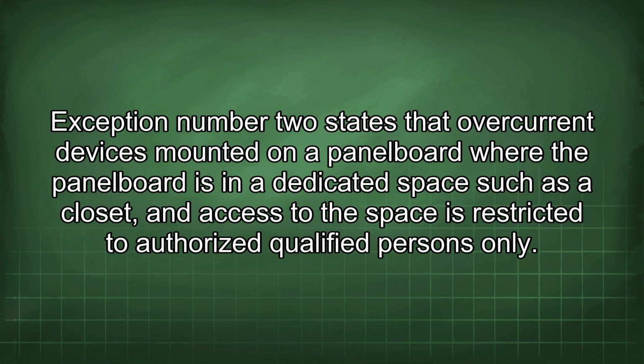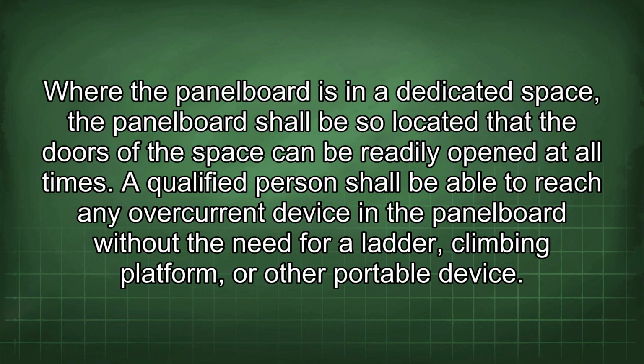Exception number 2 states that overcurrent devices mounted on a panel board, where the panel board is in a dedicated space such as a closet and access to the space is restricted to authorized qualified persons only. Where the panel board is in a dedicated space, the panel board shall be so located that the doors of the space can be readily opened at all times. A qualified person shall be able to reach any overcurrent device in the panel board without the need for a ladder, climbing platform, or other portable device.